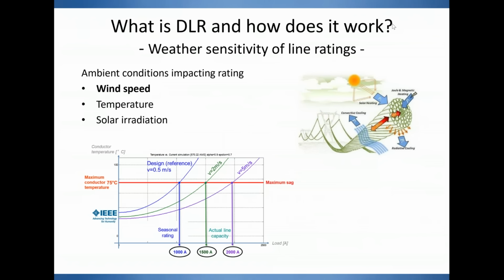So if I go a bit more into the details, this is a graph that shows that a line indeed is subject to a number of influences. One is obviously the load, the current that flows through the line, that would have a tendency to warm up the line, to heat it up, and therefore to expand its material so that the sag would increase. The other influencing factor would be the ambient temperature. If the weather is warm, obviously the line would be warmer as well, and therefore would expand more. Conversely, if the weather gets cooler, the conductor would have a tendency to cool down and therefore to sag less.